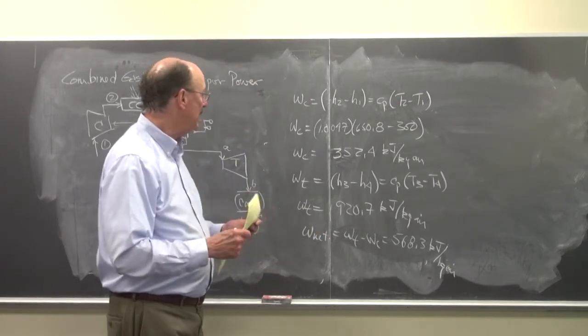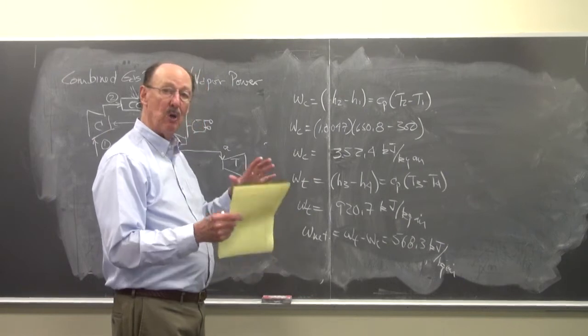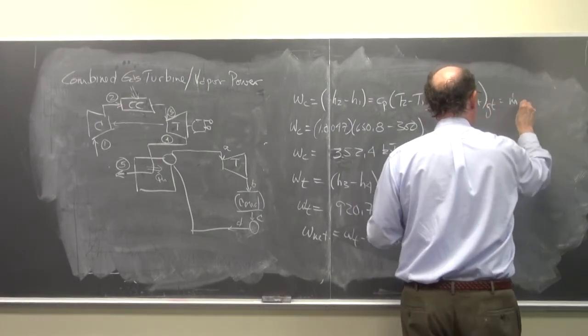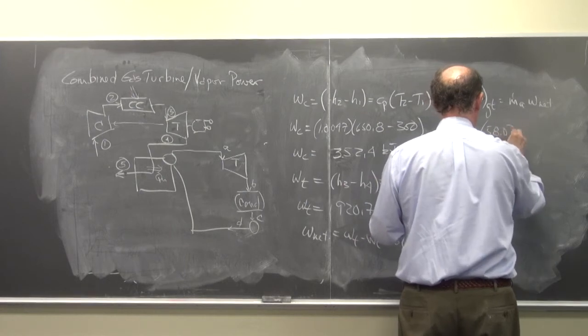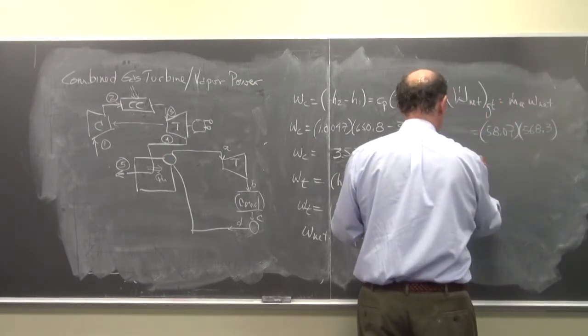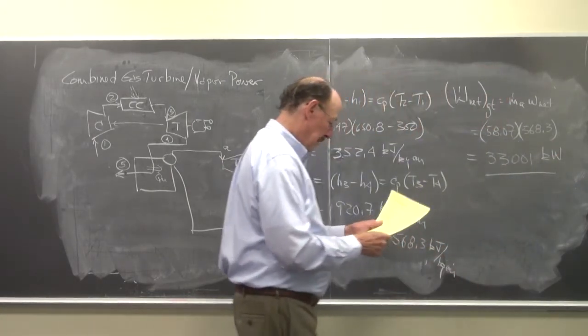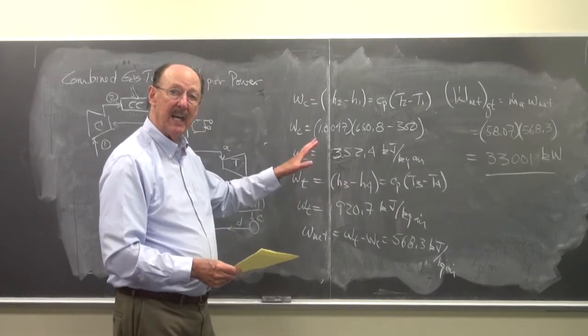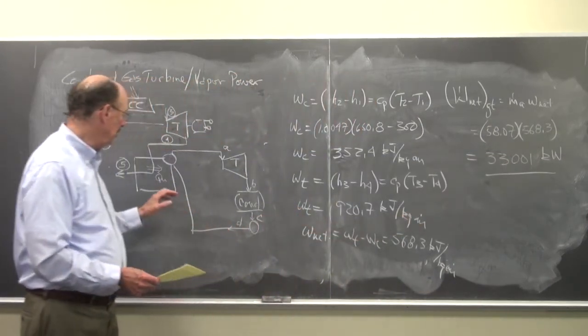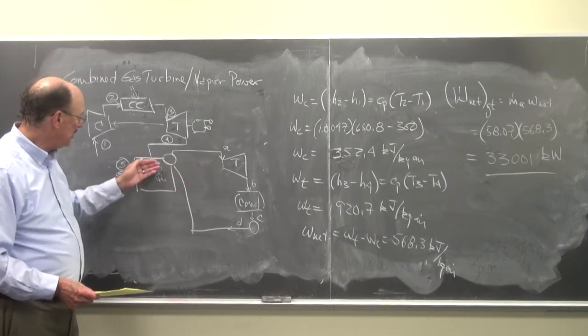And so I can find the total work because I know the mass flow rate. I found the mass flow rate earlier. So I can find the total power of the gas turbine. So W dot net gas turbine is equal to m dot air times W net. So this is equal to 58.07 times 568.3, which equals 33,001 kilowatts. So of the 61,000-something of the heat in, 33 was converted into this amount of work.